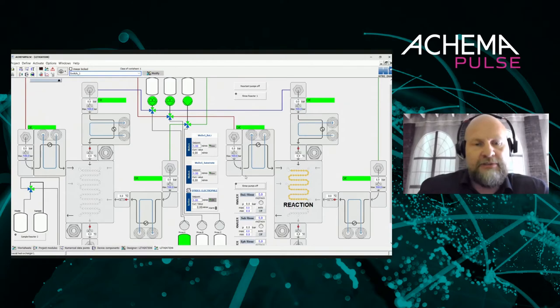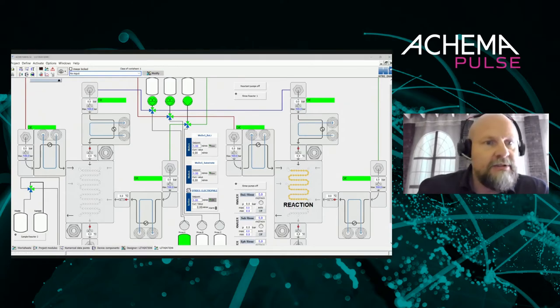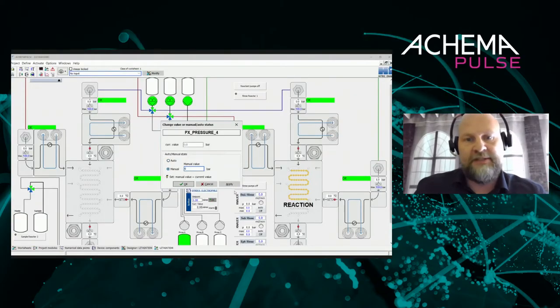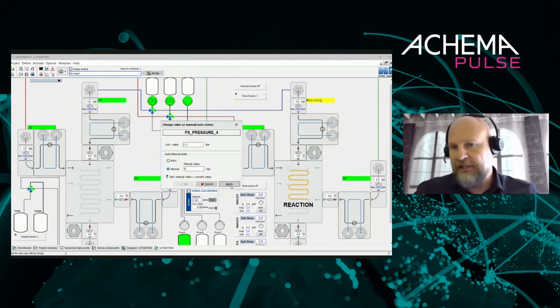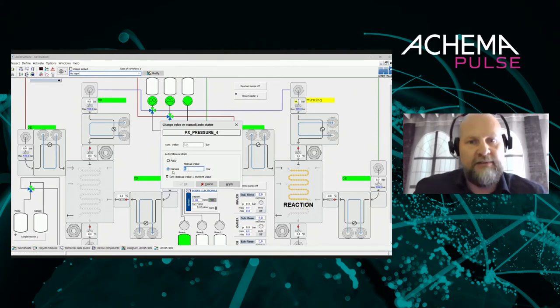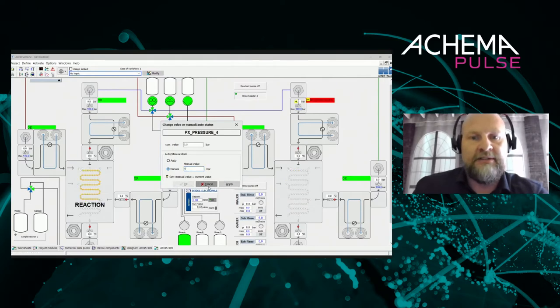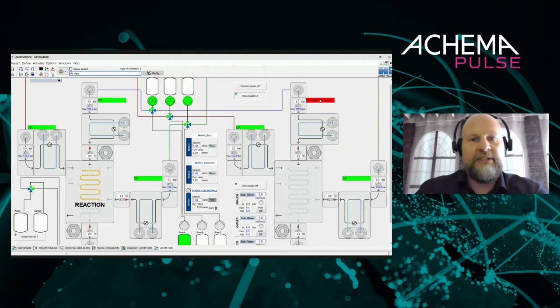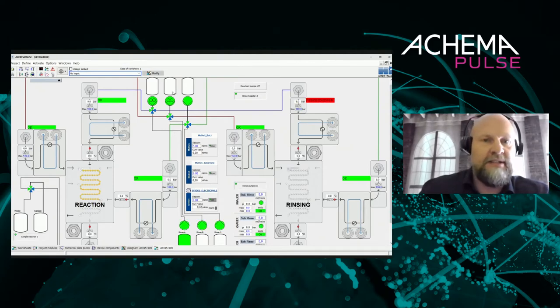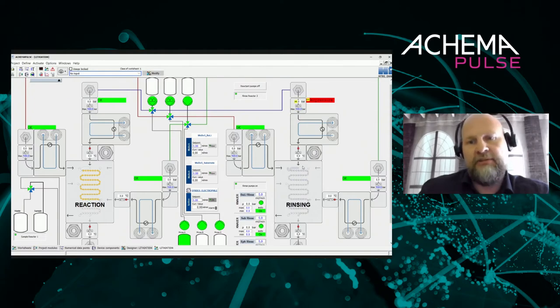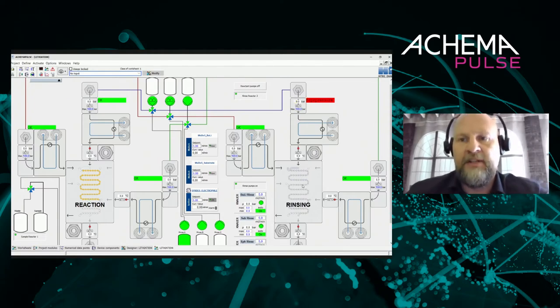Now, if we want to add some automation, I have programs already running. Let's say we have one reactor running the reaction and we experience an increase in pressure — let's say up to six bar. You can already see there is color coding, which gives the operator a warning. If the pressure goes above a certain level, an overpressure warning appears. At that point the system switches to the other reactor and the rinsing procedure starts in the first reactor.